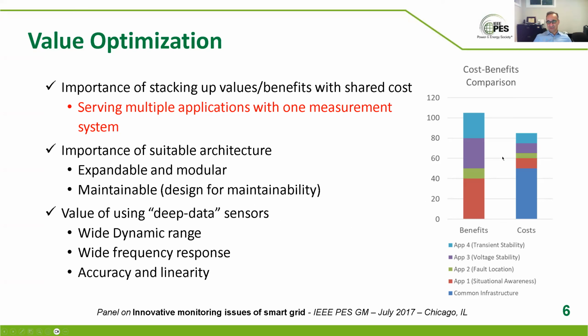This little chart, which is from a 2017 presentation at the general meeting, shows the cost of deploying technology versus benefits. Often enough, you have a base cost. Let's say the cost of putting sensors on instruments, it's a significant cost, often enough. But you still haven't done anything by just putting sensors. You've got to do something with the data you get from the sensors. For example, let's say you put in all the instrument transformers, you put all the PMUs in the field, and that's the darker blue cost on the right-hand side here.